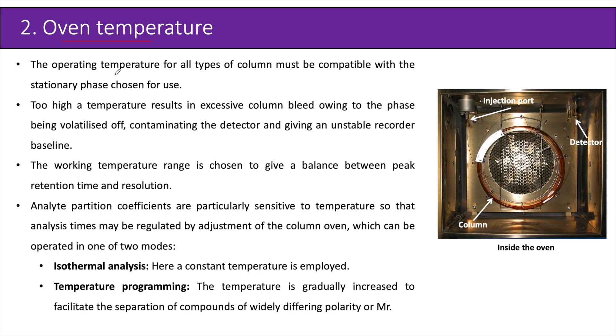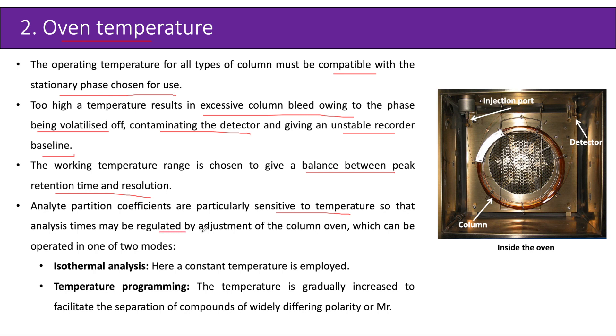Regarding oven temperature, the operating temperature for all types of columns must be compatible with the stationary phase chosen. Too high a temperature results in excessive column bleed, owing to the phase being volatilized off, contaminating the detector and giving an unstable recorder baseline. The working temperature range is chosen to give a balance between peak retention time and resolution. Analyte partition coefficients are particularly sensitive to temperature, so analysis times may be regulated by adjustment of the column oven, which can be operated in one of two modes. The first is isothermal analysis, where a constant temperature is employed.